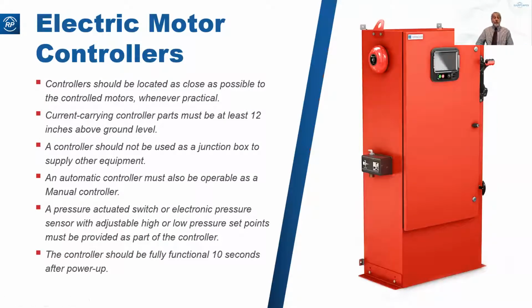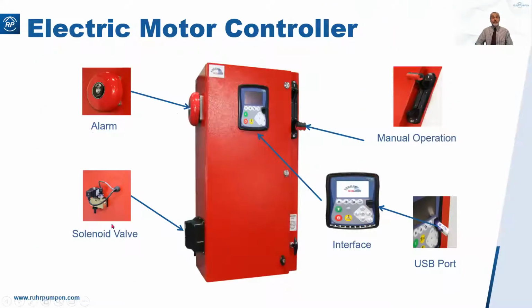The motor panels, here's a motor starter. They can be direct online, across the line, you Americans tend to say, star delta, Y delta, and auto transformer start. They are acceptable. You'll see that there's a pressure transducer for auto start on drop of pressure with an adjustable time delay. There's also a solenoid valve for the weekly test start. You would trigger that, it would drop the pressure in the system and thus bring the pump in.